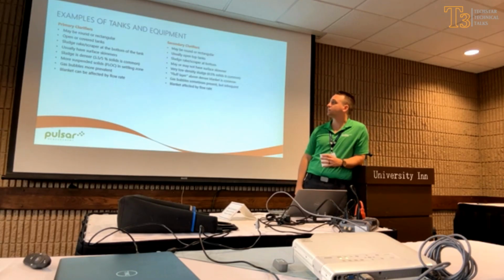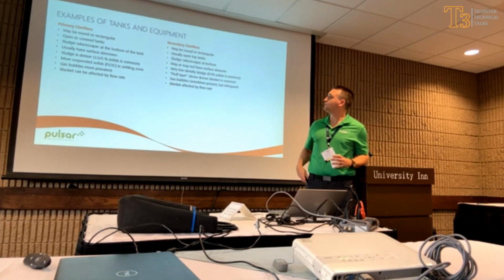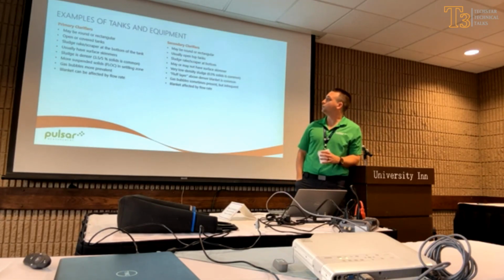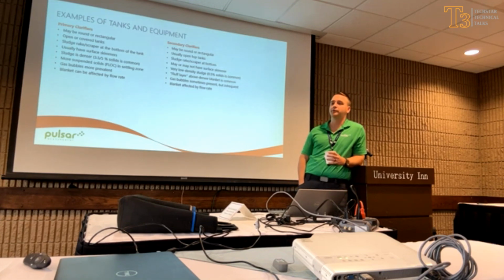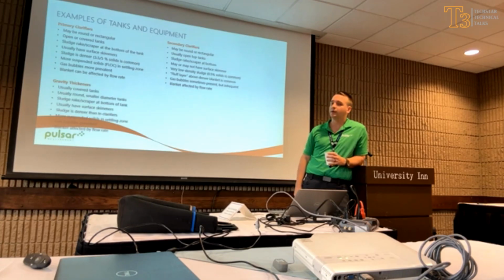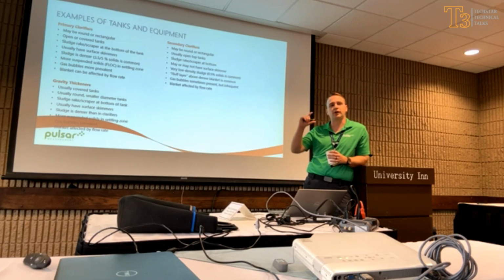Okay, so secondaries, similar process, but now we've already gone through, so we're going to be looking at lower density sludge, typically even down to 0.5% solids, with some outgassing being prevalent, but not that much. Does anybody run any thickeners? There's some thickeners. Okay cool, my thickener guys. It's usually smaller tanks, you're going to be building up a really thick blanket as compared to the others, and it's typically a bit more of a challenging measurement. What levels do y'all typically run in your thickeners as far as a desired set point? 5%. 5%, yep, pretty common.